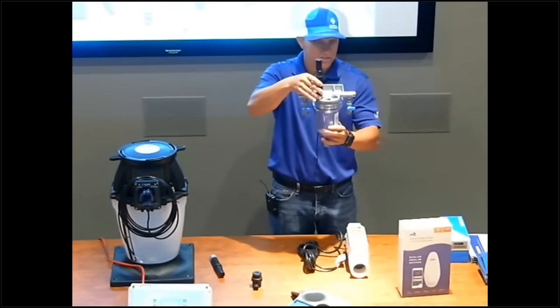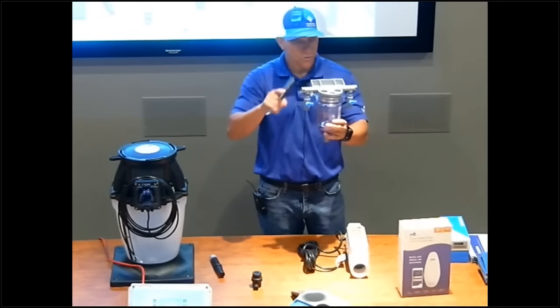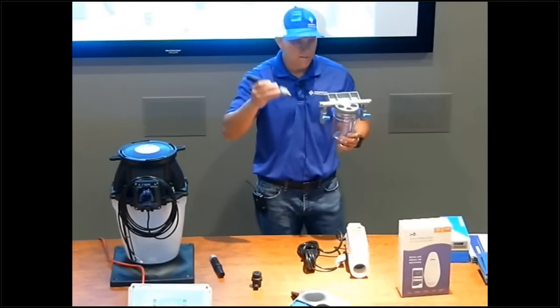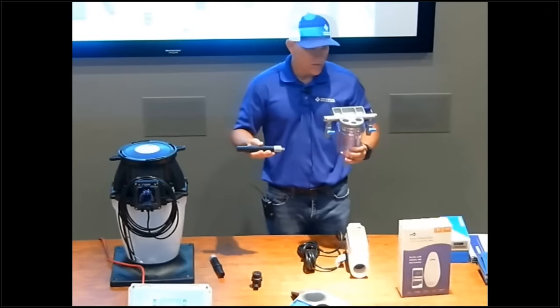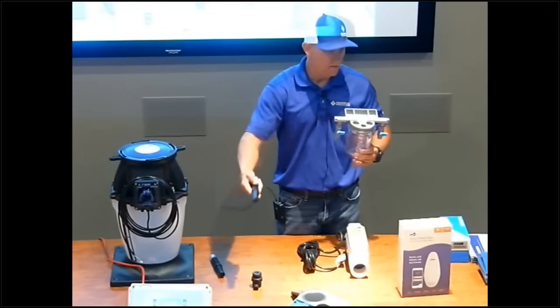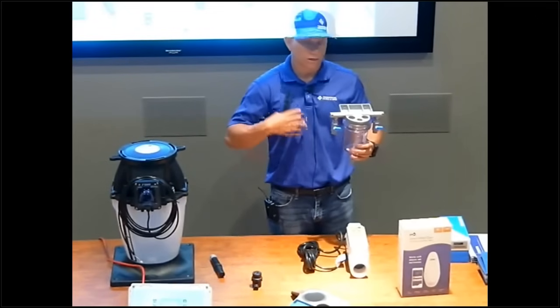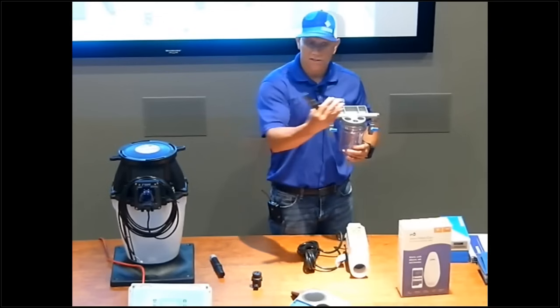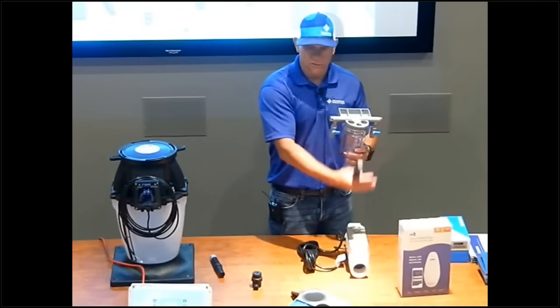So these two probes sit in here, and as the water comes across the probe tip, it registers the information to the control box. The control box then says, do I need to adjust the pH, or do I need to adjust the ORP, which is the free chlorine, okay?